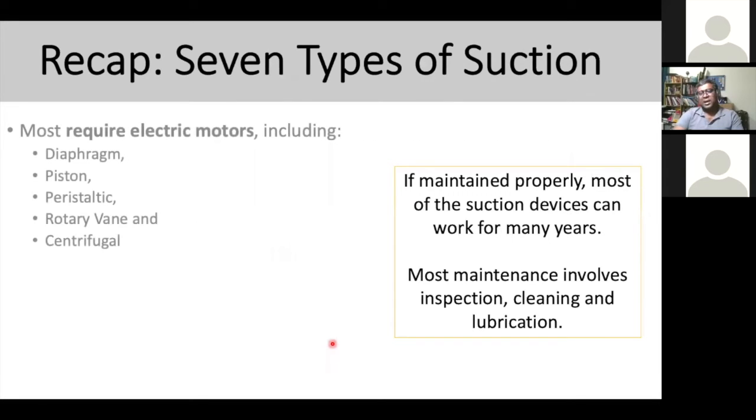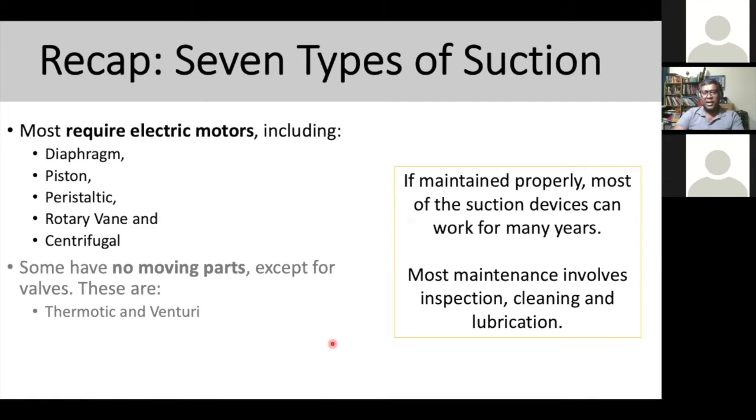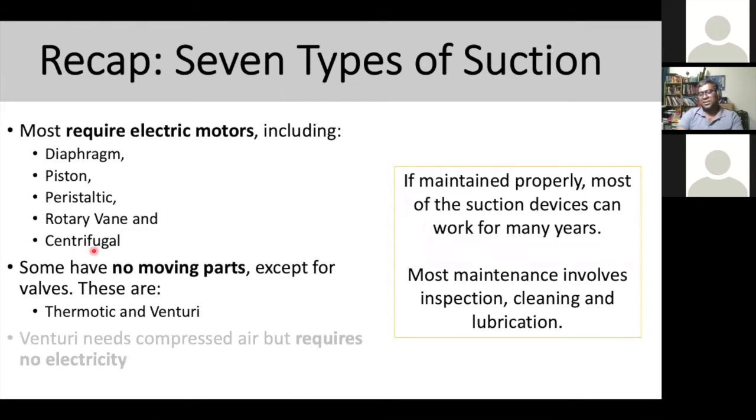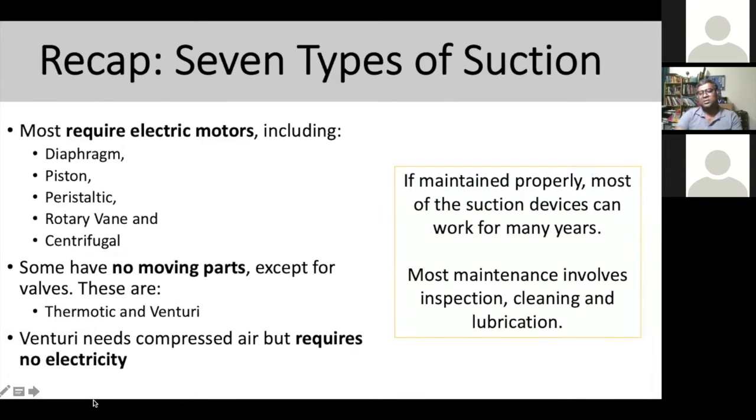To recap the seven types of suction pumps: most require an electric motor — these include diaphragm, piston, peristaltic, rotary vane, and centrifugal. Some have no moving parts except valves, like Thermotic and Venturi. Venturi needs compressed air but requires no electricity. These are the seven types you'll commonly see in hospitals. If you maintain them properly, these devices will work for many years. Most maintenance involves inspection, cleaning, and lubrication.